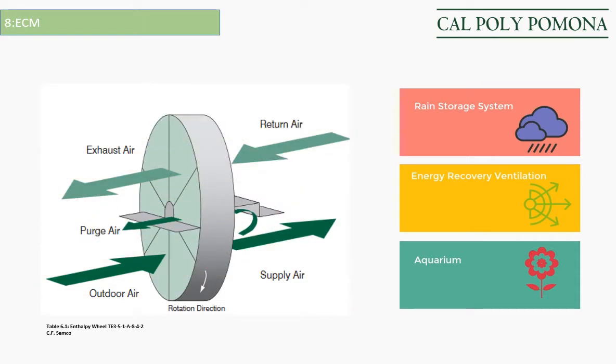Energy recovery is not installed into the service stalls and parking garage because of polluted exhaust air leaking into the supply. If a tight construction can be made with no leakage, 30 MBH can be saved by adding an energy recovery wheel.